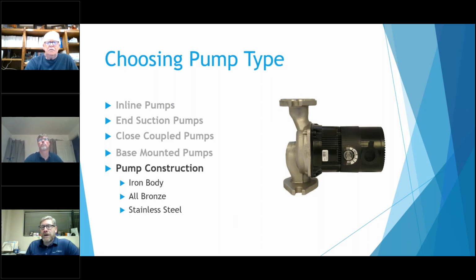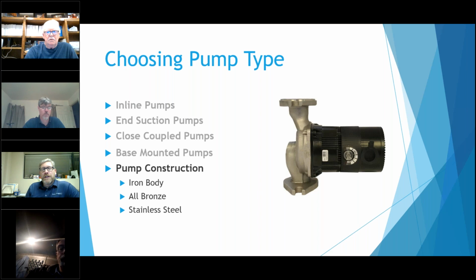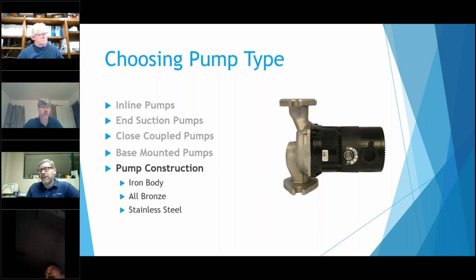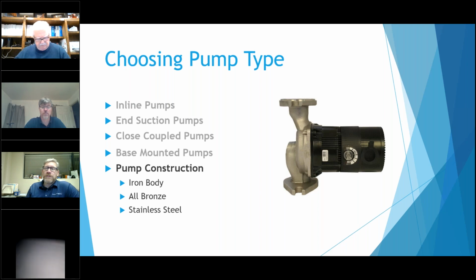You can also use the stainless steel pumps on a lot of process type applications. Then the other main thing you have to look out for as far as pump types: on a lot of the bigger pumps, they can get different seals. The Buna-carbon-ceramic is kind of the standard that works for almost all applications. When you get to some of the glycol applications, you need a little bit better seal. With some of the high pressure applications, you need a much stronger seal than that can provide. So some of the pumps that are picked are also dictated by what that seal needs to be. You might have a small pump where you need a better seal, so you'd have to go to a larger pump to use that type of seal.